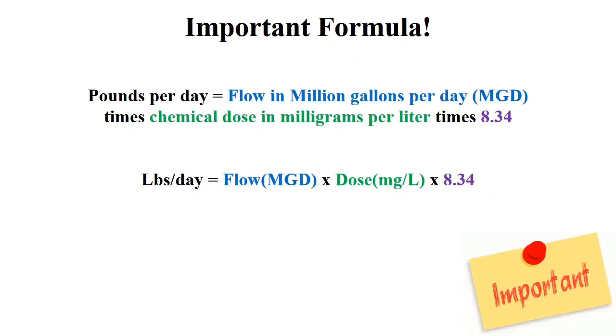An important formula for calculating feed rate is: pounds per day equals flow in million gallons per day (MGD), times the dose in milligrams per liter, times the constant 8.34.